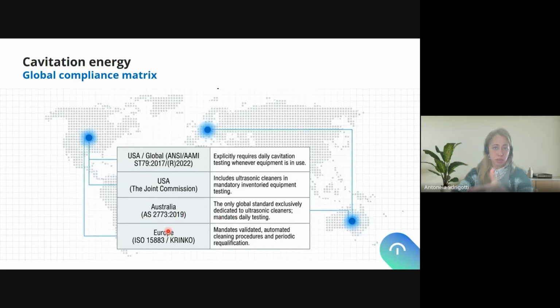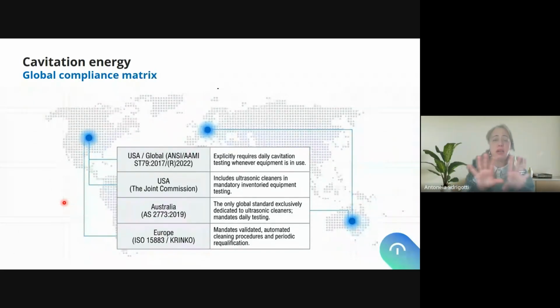And just a few examples in Europe, the ISO 15883, we say Europe, but it's actually an international standard. And the KRINKO, German recommendations, mandates validated automated cleaning procedures and periodic requalification. So these are just a few examples. We also have HTM. We also have APSIC guidelines. There are many localized recommendations so as to monitor, to be sure that our ultrasonic washers are performing correctly. Not all of them, of course, mandate to do this on a daily basis, but it is important to notice that standards talk about this and that the washer needs to be validated.